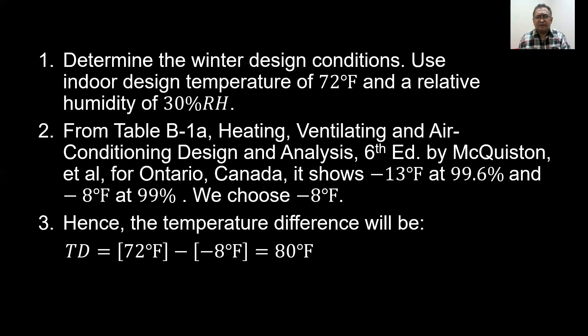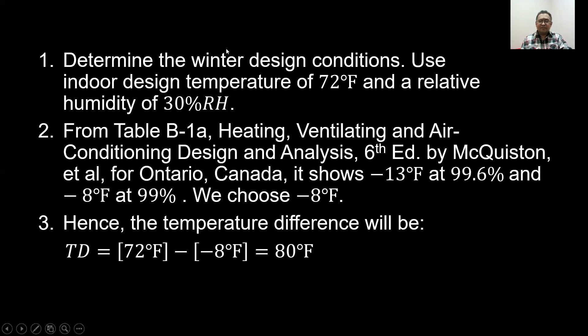Determine the winter design conditions. Use an indoor design temperature of 72°F and a relative humidity of 30%. From table B-1A, heating, ventilating, and air conditioning design and analysis, sixth edition by McQuiston, for Ontario, Canada, it shows outdoor conditions of negative 13°F at 99.6% and negative 8°F at 99%. We choose minus 8°F. Hence, the temperature difference will be 72°F minus negative 8°F, which equals 80 degrees Fahrenheit.